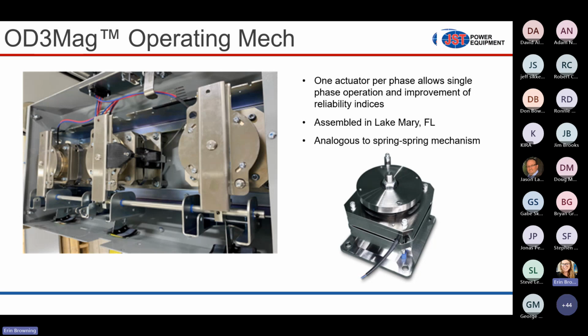They use dual coil actuators where you have a top coil and a bottom coil, and each coil is responsible for an upward or a downward motion. Our actuator is one coil that can do both up and down motions depending on the polarity of the voltage that we apply to it. So it's a simplified, consolidated, smaller footprint actuator. Again, it's the same type of actuator that's used in reclosers, and because we're applying it to our circuit breaker, it's small and compact enough to do one per phase, which allows us to do single phase trip, single phase close. With the dual coil actuators that ABB and Siemens are using, those are a lot bigger. You can't put three of them in one breaker to do single phase trip, single phase close. It would be a much bigger breaker.